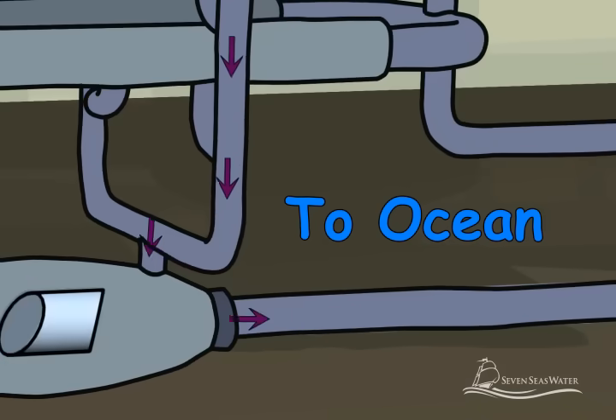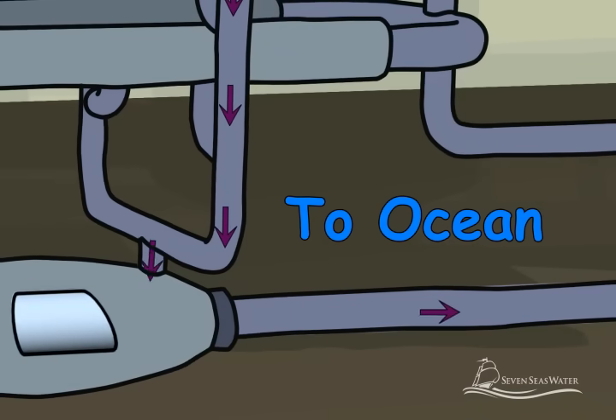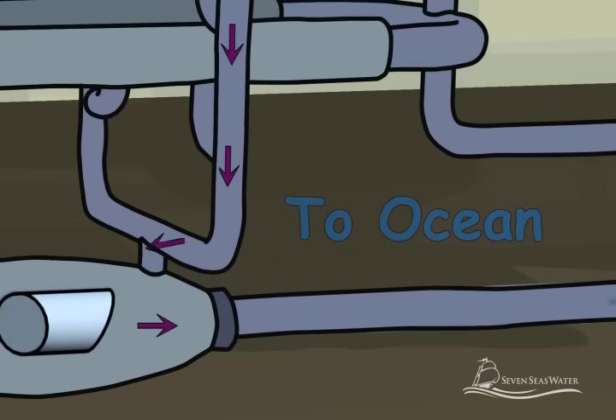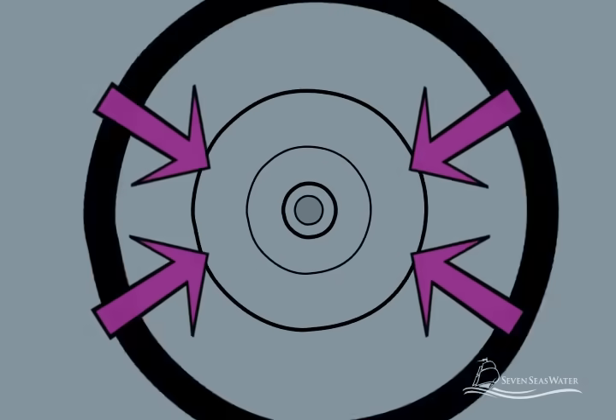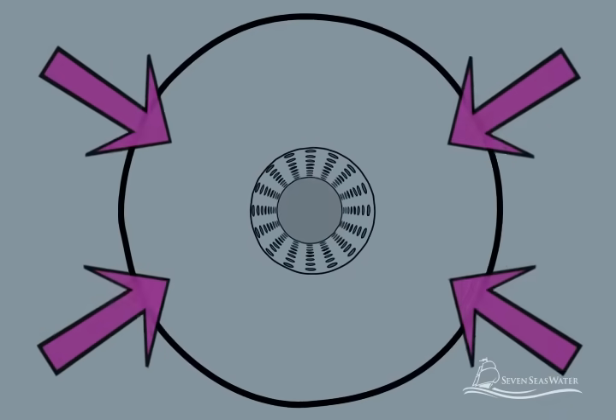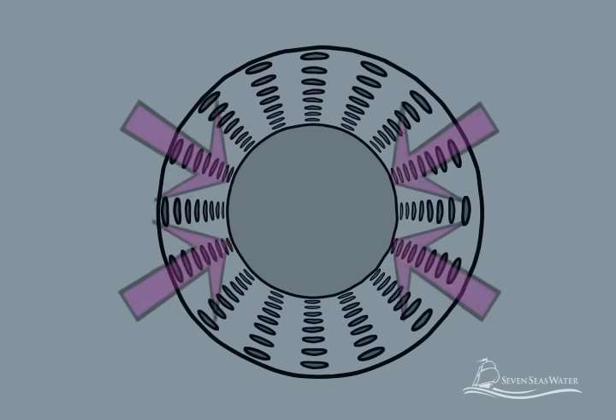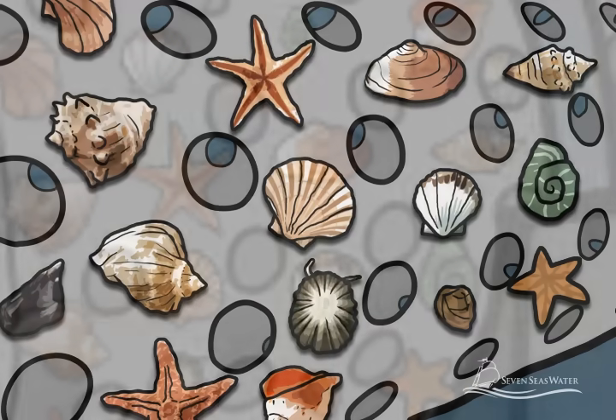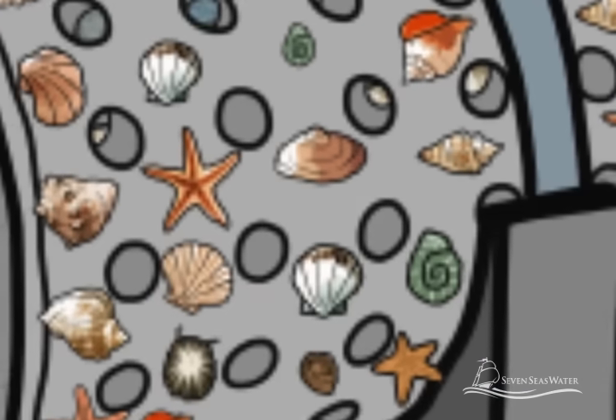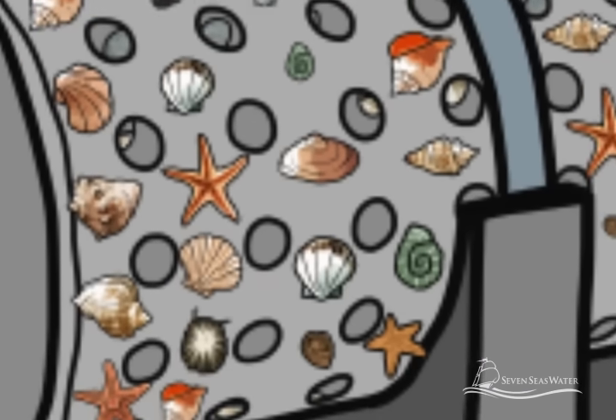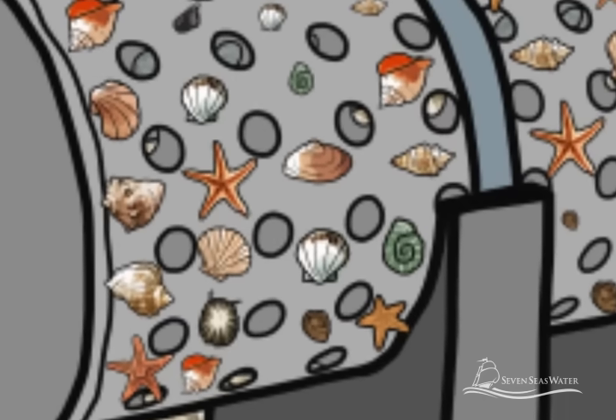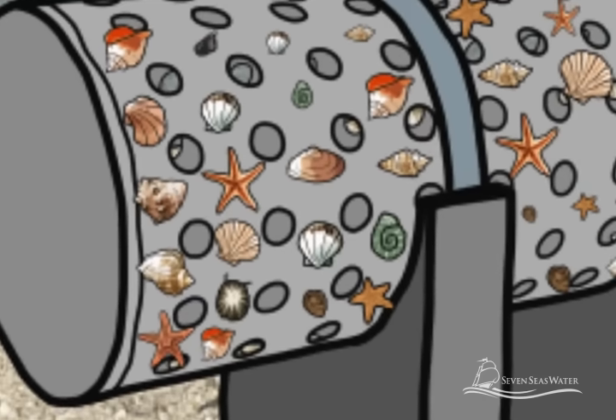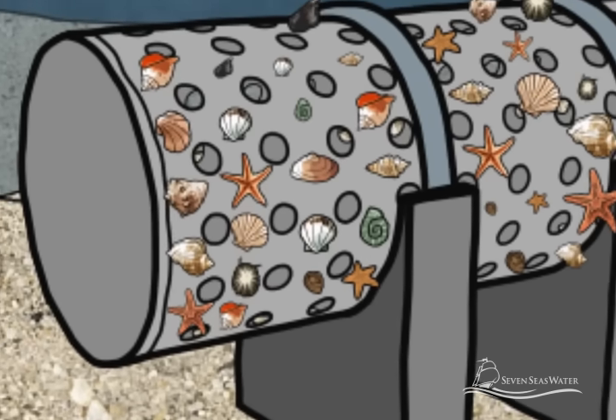The concentrated salt stream will have about a 60% higher salinity than the incoming seawater. The concentrated salt stream is sent back to the ocean through a brine disposal well, or a device known as a brine outfall. The brine outfall is situated in an area of significant ocean flow so that the salt levels are quickly returned to equilibrium with the ocean. The location for the outfall should contain no sensitive marine ecosystems.